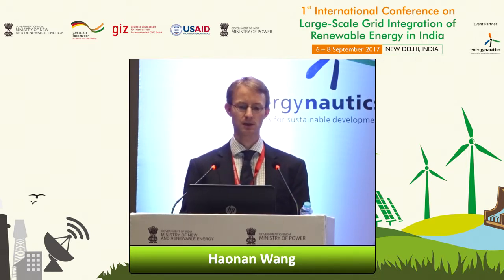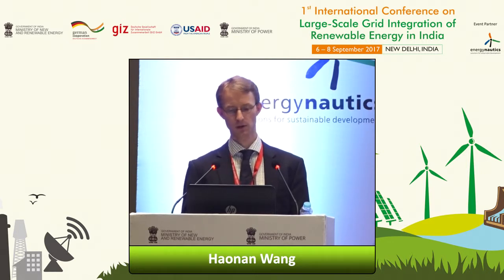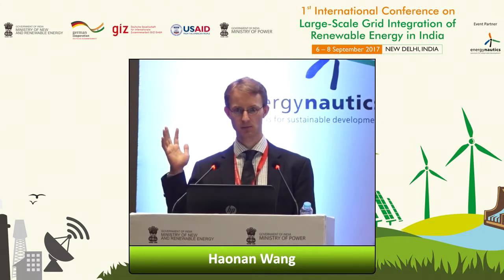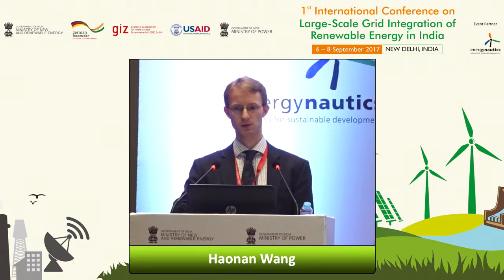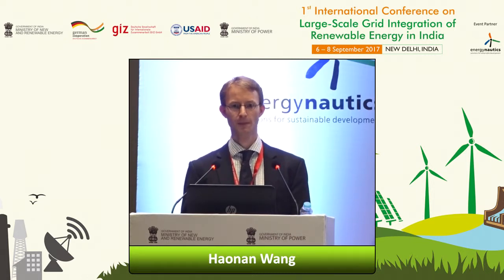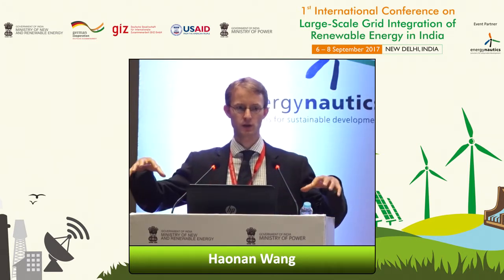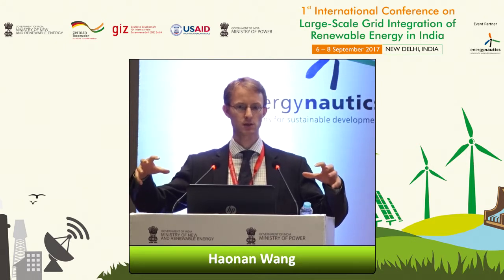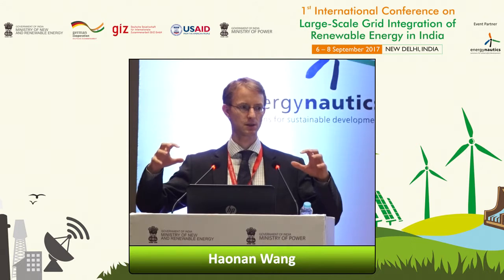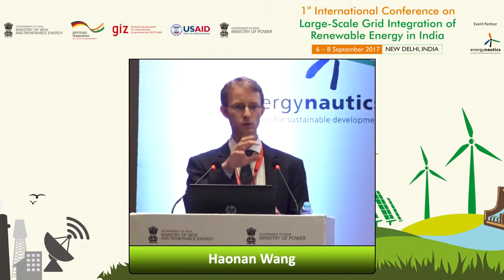interacting. And so we designed, with a lot of effort over many years now, a simulation platform, a co-simulation platform, which allows us to run real-time simulations and offline simulations. We are now calculating with 100,000 nodes, grids across 3 to 4 voltage levels, so we can really run a full system calculation in real time. And so we can analyze different interactions on the real grid. We are running real-time simulations, simulating the plants and the network in detail, with power flow calculations or RMS simulations, and then we apply different operational tools on different voltage levels.